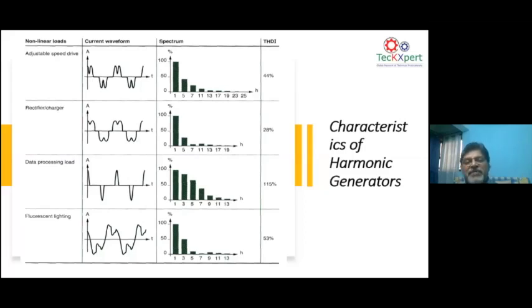Sometimes if you buy a VFD which does not have a line reactor or a DC choke, this 44% becomes 85%. So when you buy a VFD, if you want to ensure it is below 40%, you should have an input line reactor or a DC choke. Now, a conventional rectifier is more or less the same as a VFD, because a rectifier is nothing but a device that converts AC to DC. So at the input of the AC side, you will see the wave shape is like this. It has 5, 7, 11, 13 harmonics.